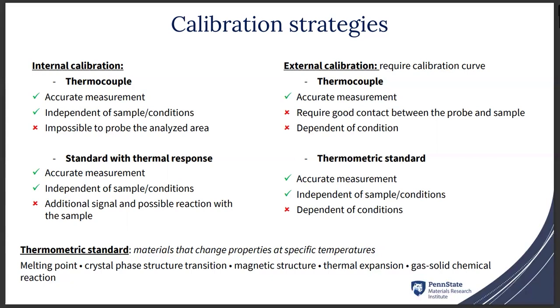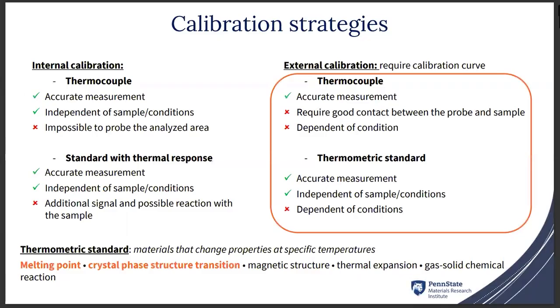The second possibility, which is what is used for TGA, is using a thermometric standard. So when I'm talking about a thermometric standard, I'm talking about a material that changes its property at a specific temperature. So the property can be the melting point, crystal phase structure transition, magnetic structure, this is what we saw for the TGA, thermal expansion, or gas-solid chemical reaction. So the advantage of the thermometric standard is it is accurate, but depends on the conditions. So today I will be talking exclusively about external calibration for two particular accessories, one for FTIR, one for XRD. And I will use a thermometric standard with specific melting point or phase structure transition.